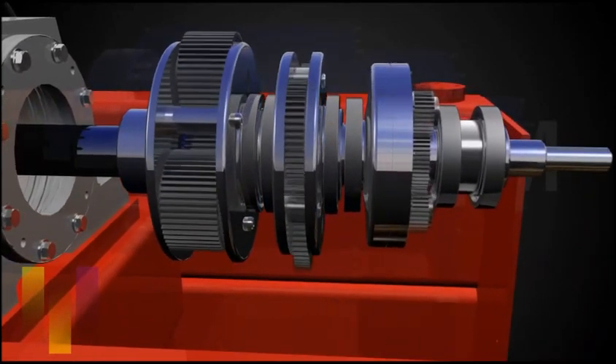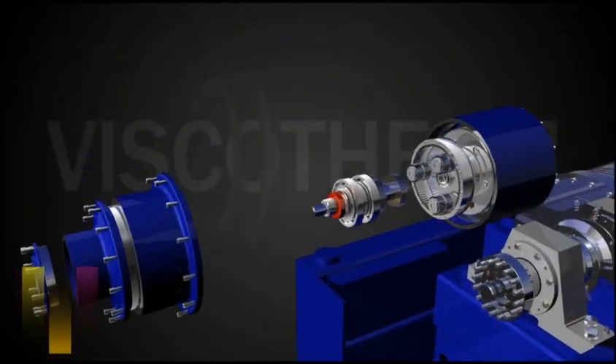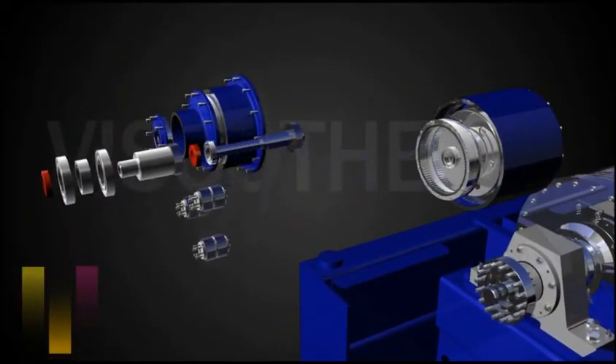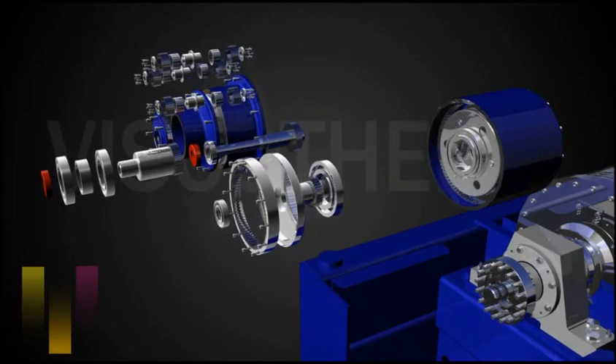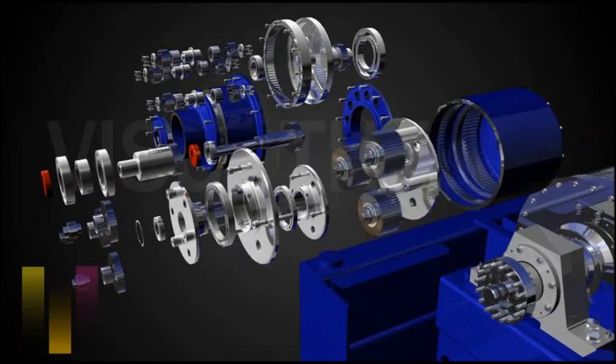Overheating of gearboxes is a common problem due to inadequate lubrication of the gears located in the center of the box. The centrifugal force distributes the oil towards the outside wall of the gearbox, away from the center gears.